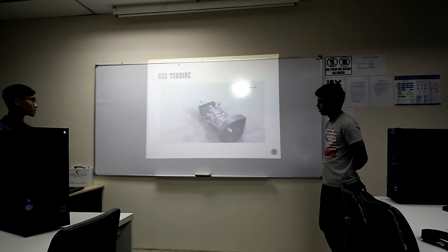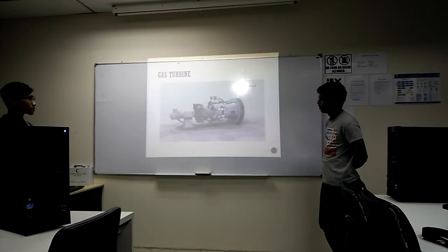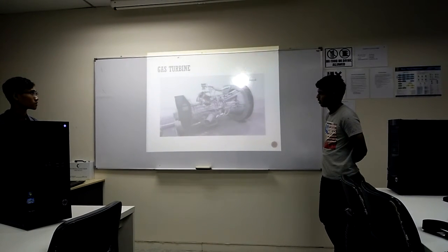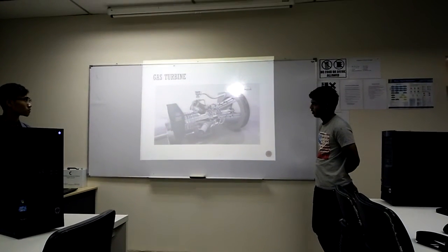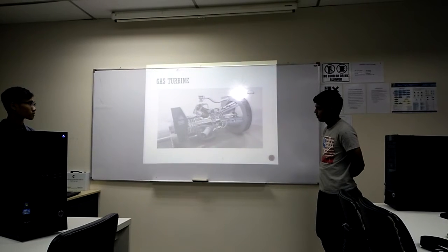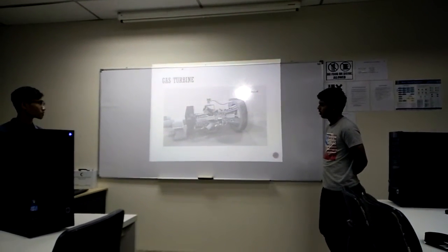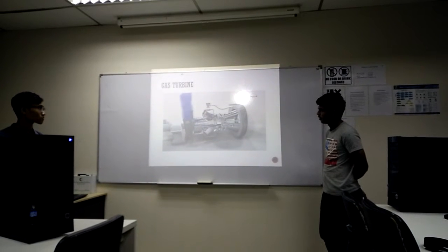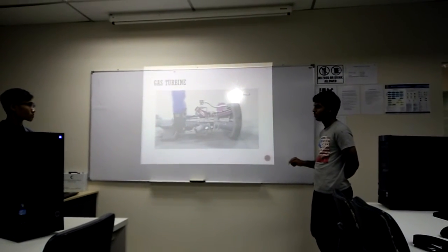This is equivalent to 9,522 horsepower, thus as much as 95 automobile engines of 100 horsepower each produced together. The MGT6200 basically comprises two sections, the gas generator with high pressure turbine on the left, and the power or low pressure turbine on the right, which runs independently of the gas generator at a variable speed thanks to a second shaft. External drive starts the gas turbine. In this case, it is an electric motor which drives the shaft of the high pressure turbine and along with this, the 11-stage axial compressor mounted on it. The compressor driven by the high pressure turbine serves to take in and compress the air needed for combustion. Inside the six combustion chambers, the air is mixed with fuel.